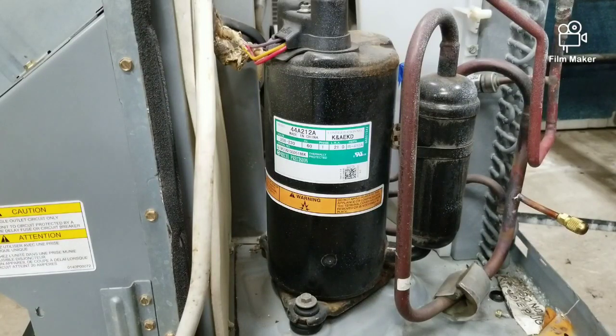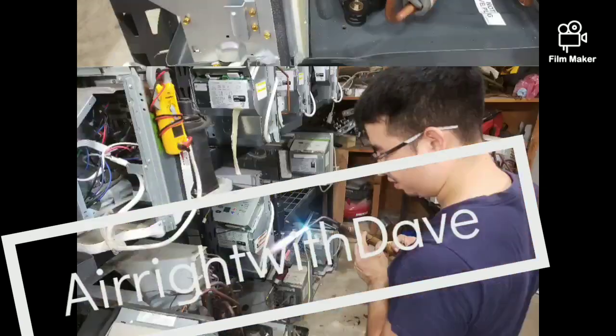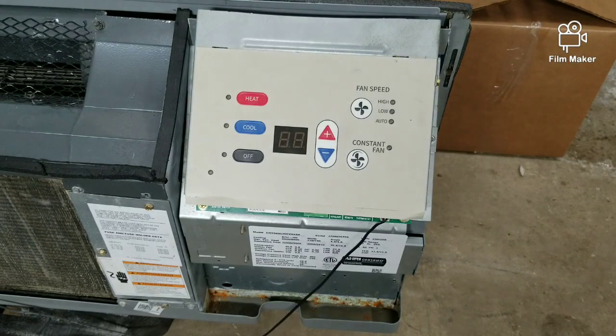What's going on everybody? I went out to a property and they had a PTAC unit that wasn't cooling. Turns out the compressor wasn't coming on — it was trying but it wasn't coming on. Turns out it was a bad capacitor. In this video I'll be showing you guys how to test your dual capacitor. This is Airright with Dave, welcome to the channel everybody.